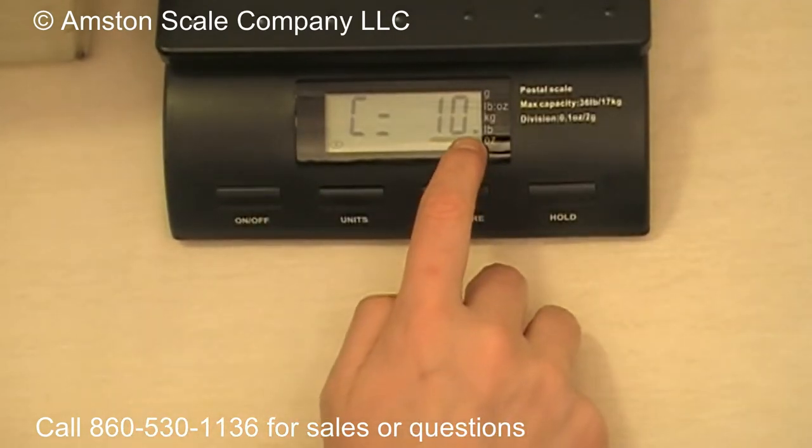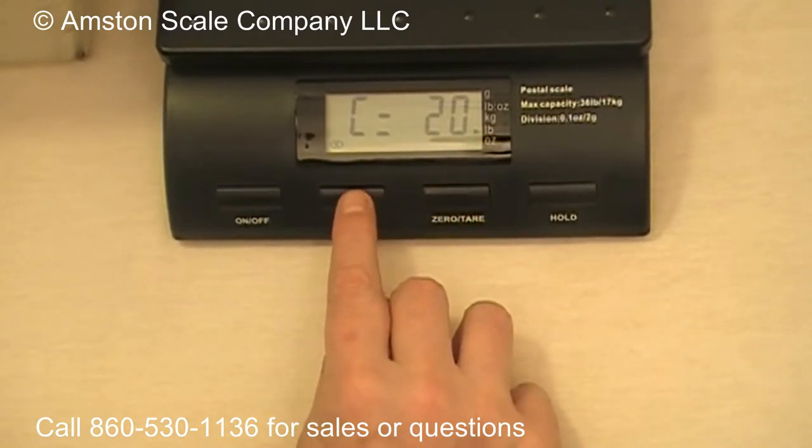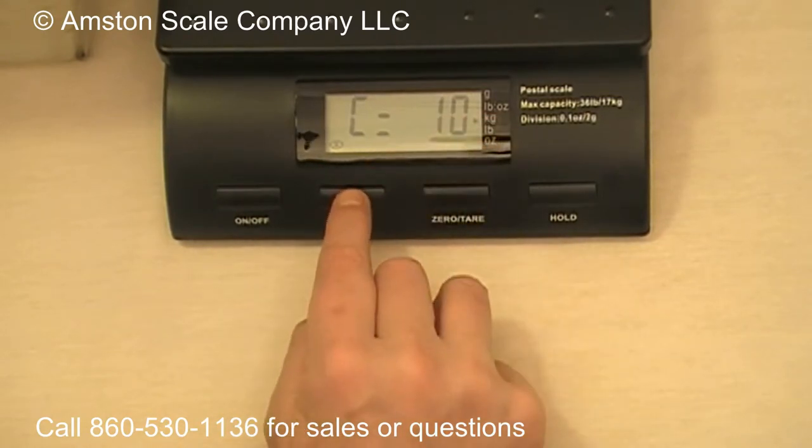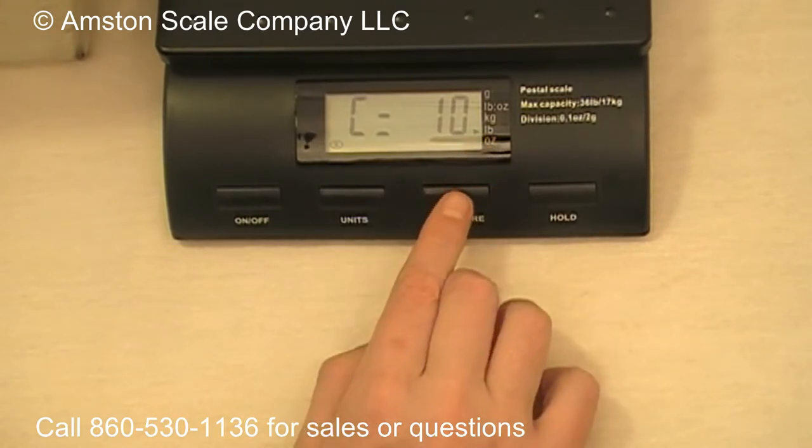You want to make sure that the scale is pointing to pounds. If it's not and you want to change that, press the Units button. It's calibrated at 10 pounds, 20 pounds, now it's 10 kilograms. Press the Unit button again and now the calibration weight is 10 pounds.